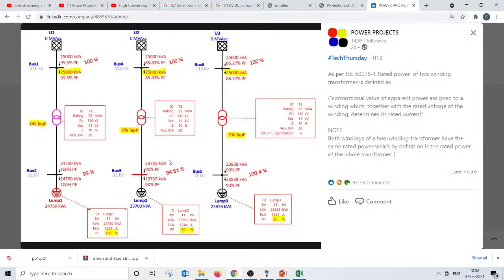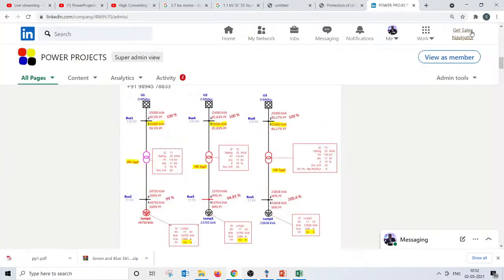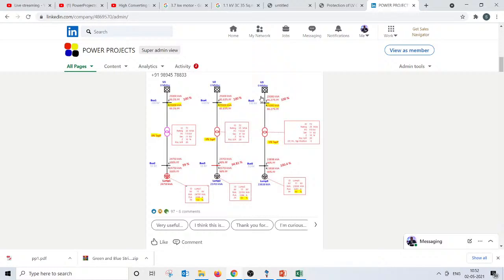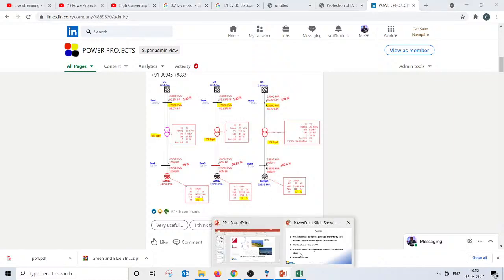And even for that, your voltage is like 94.81 percent, with the same power factor. But if you allow the transformer tap to change to regulate this voltage, then probably you can also load this transformer slightly better, like 23.838 MVA, right? So try this exercise with different power factors and different grid voltages, then you will understand a lot more, right? So probably that's what I thought of conveying.